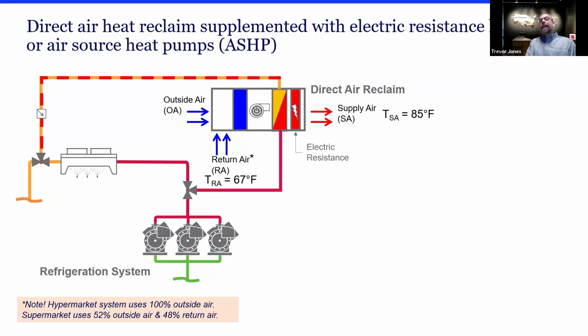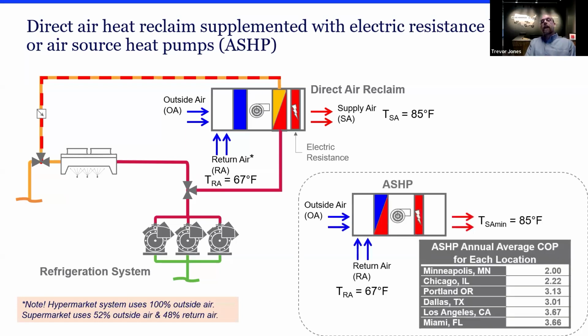For supplemental heat, we looked at electric resistance heat. We also looked at air source heat pumps as an additional option for reducing carbon and reducing gas usage. Air source heat pumps have a better coefficient of performance because they're pulling heat out of the atmosphere. They work much better in warmer climates than they do in, say, Minneapolis, but there's still a significant amount of time, even in cold climates, where you can get a fair amount of heat through an air source heat pump. And we're listing out the average COP that we were using for each location.